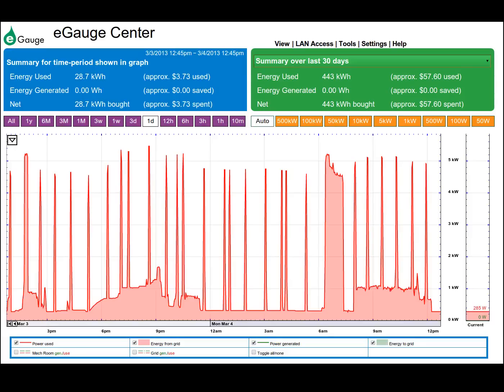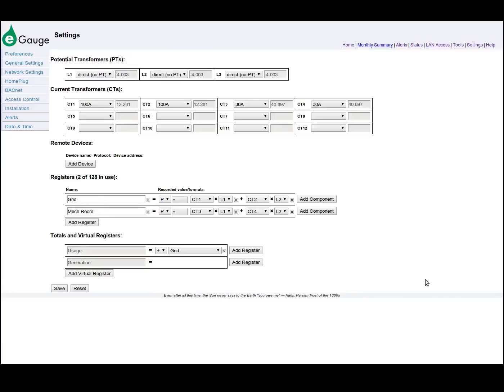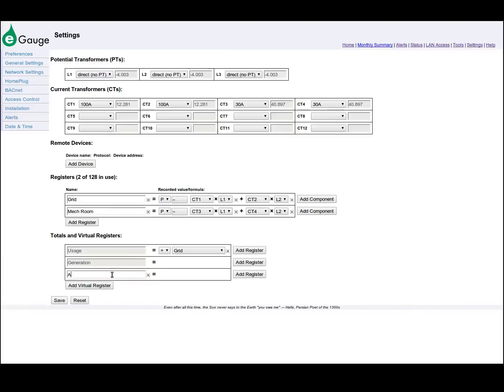Views can be used to define a restricted or alternate view of the data recorded by an E-Gauge device. For example, views could be used to view the usage and/or generation data for an individual condo when a single E-Gauge device is used to monitor several units. The standard view of all registers is referred to simply as default. A view is defined in the virtual registers by prepending the view name and a dot in front of a register name.